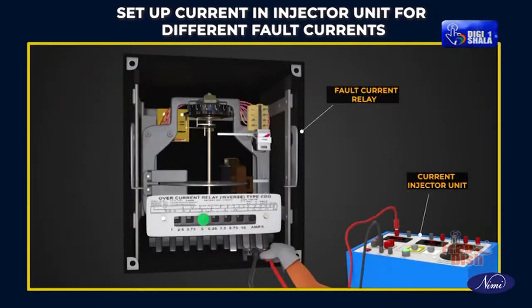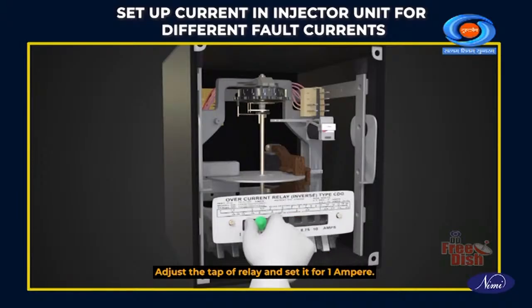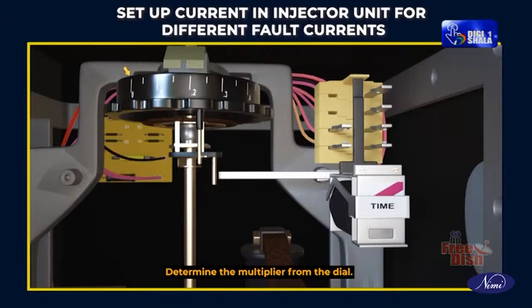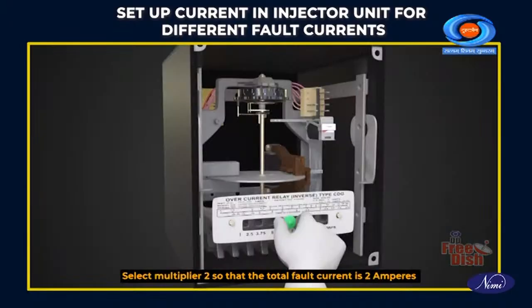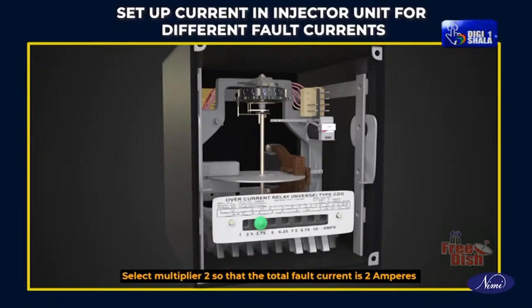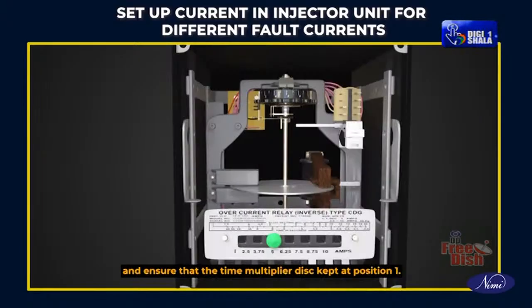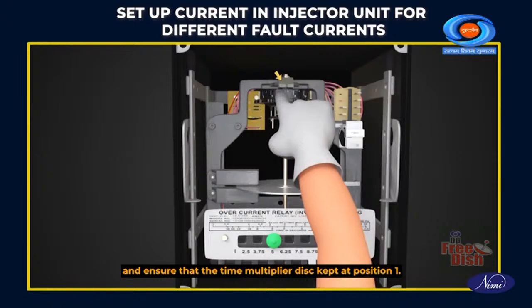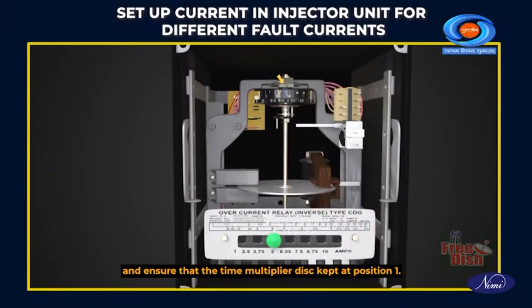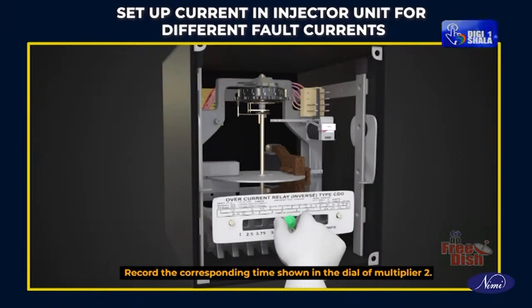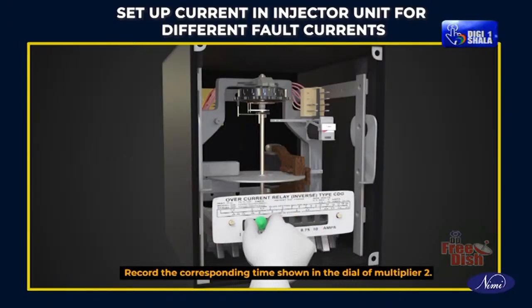Set up the current in the injector unit for different fault currents. Adjust the tap of the relay and set it for 1 ampere. Determine the multiplier from the dial. Note down the values. Select multiplier 2 so that the total fault current is 2 amperes, and ensure that the time multiplier disc is kept at position 1. Record the corresponding time shown in the dial of multiplier 2.